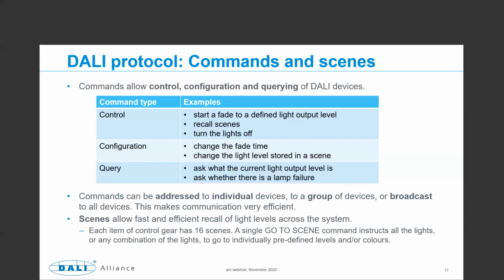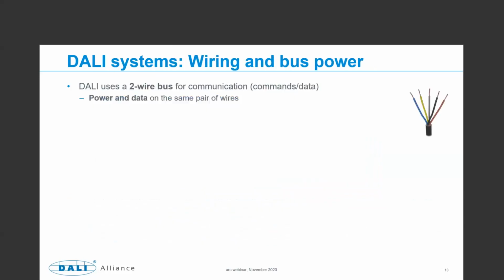So the wiring and bus power. I mentioned earlier, DALI uses a 2-wire bus for communication and data. The power and data is on the same wires. So the picture there shows a 5-core cable, and that's typical of an installation where you've got the mains supply going to the luminaires, as well as the 2 wires for DALI, all bundled into the same cable. So it's very convenient and quick for wiring.